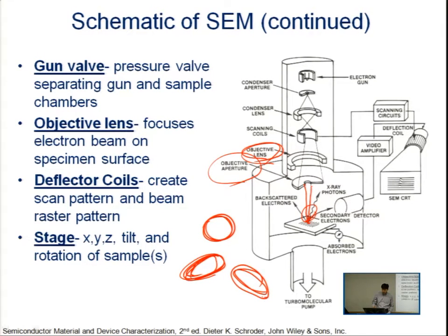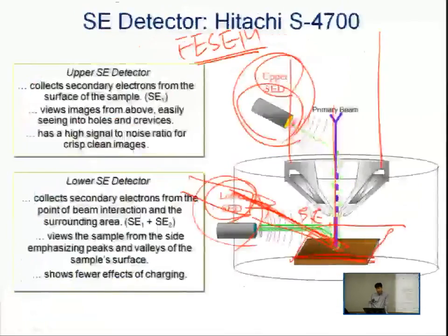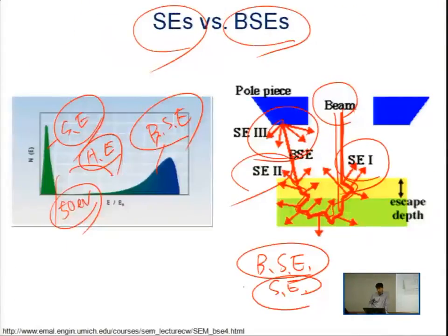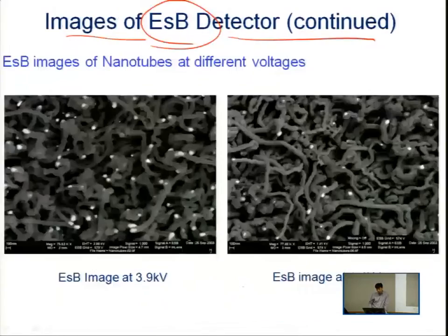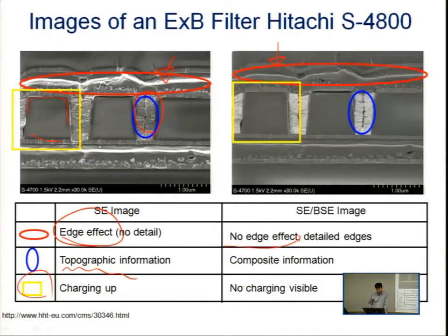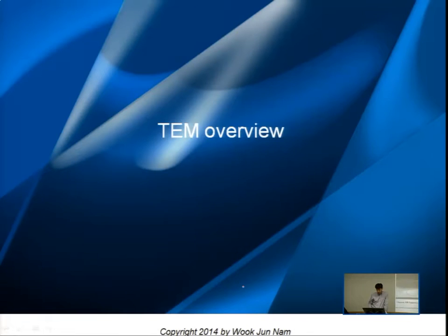That ellipse shape of the primary electron beam makes the final images much blurrier. So in that case, we control the stigmator to make the primary electron beam a more perfect circle. So that is that application.